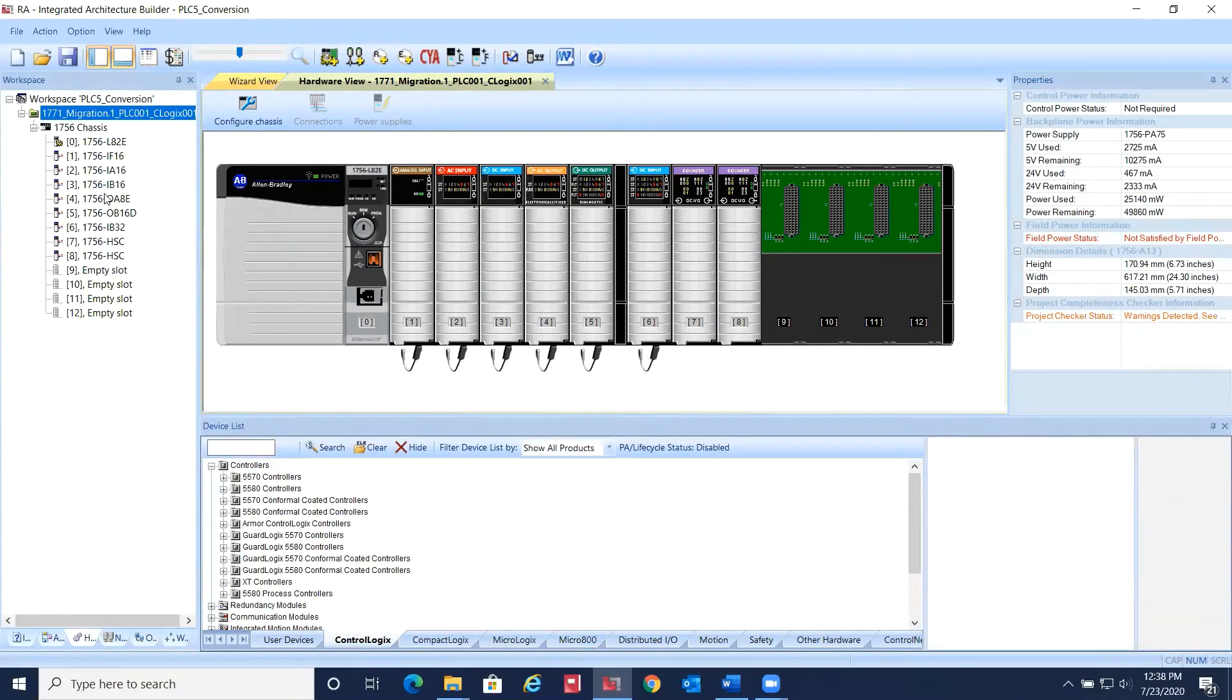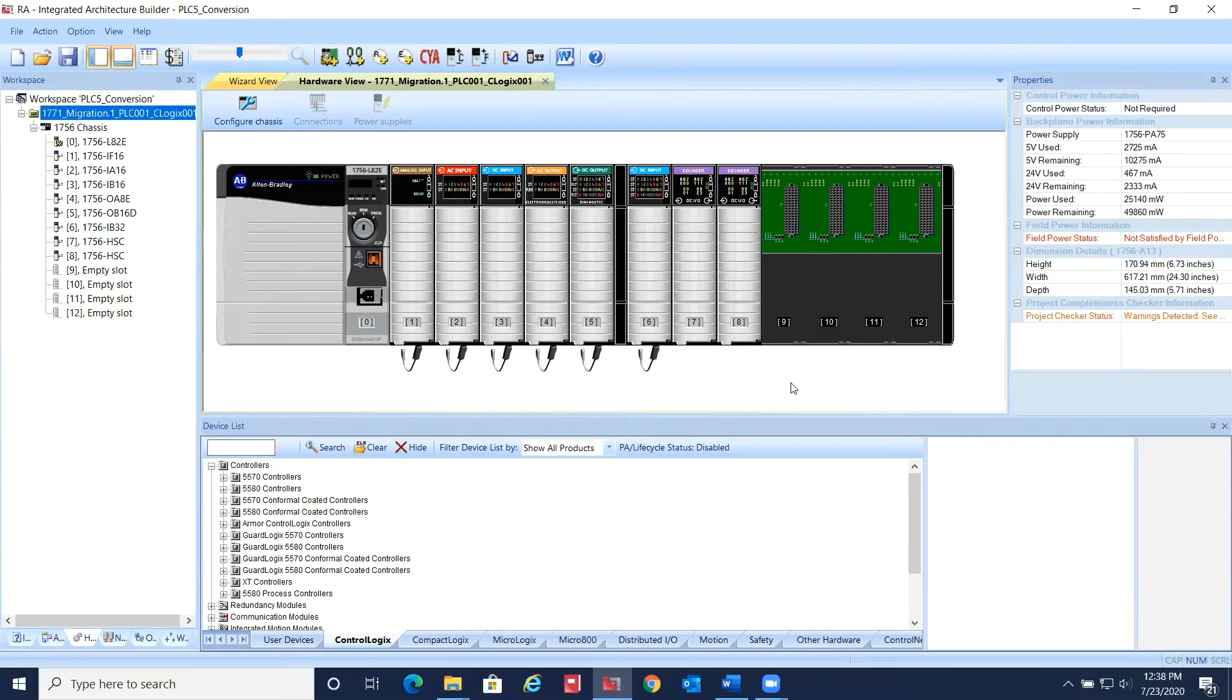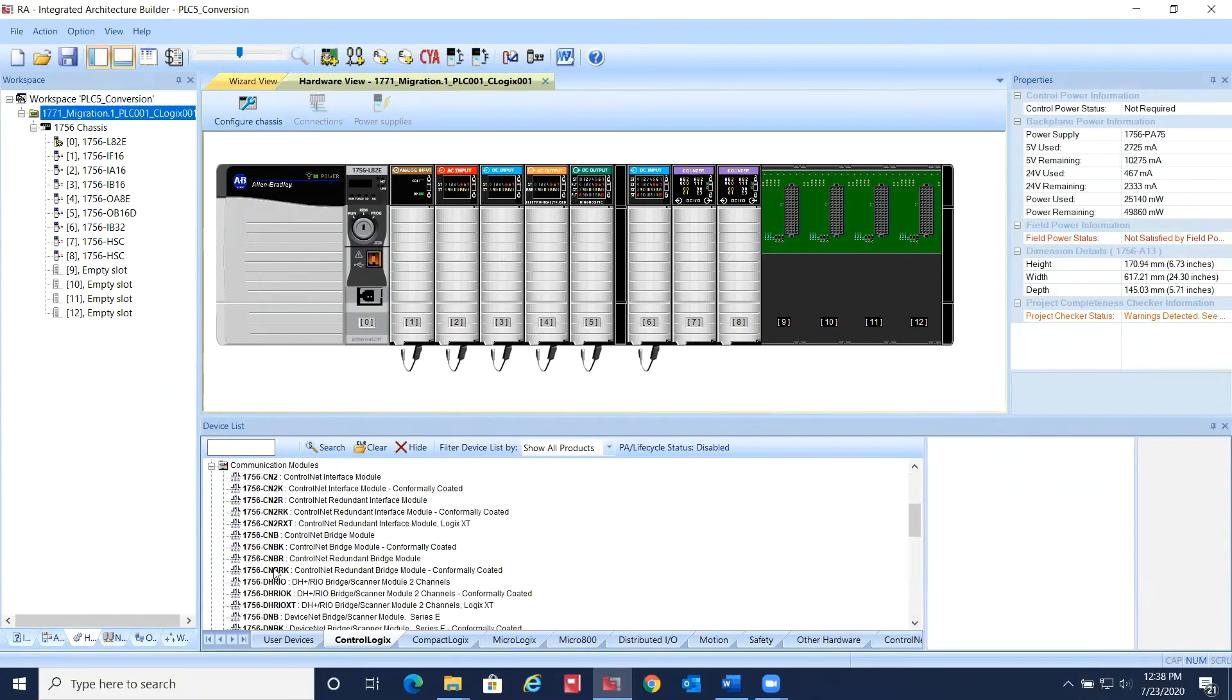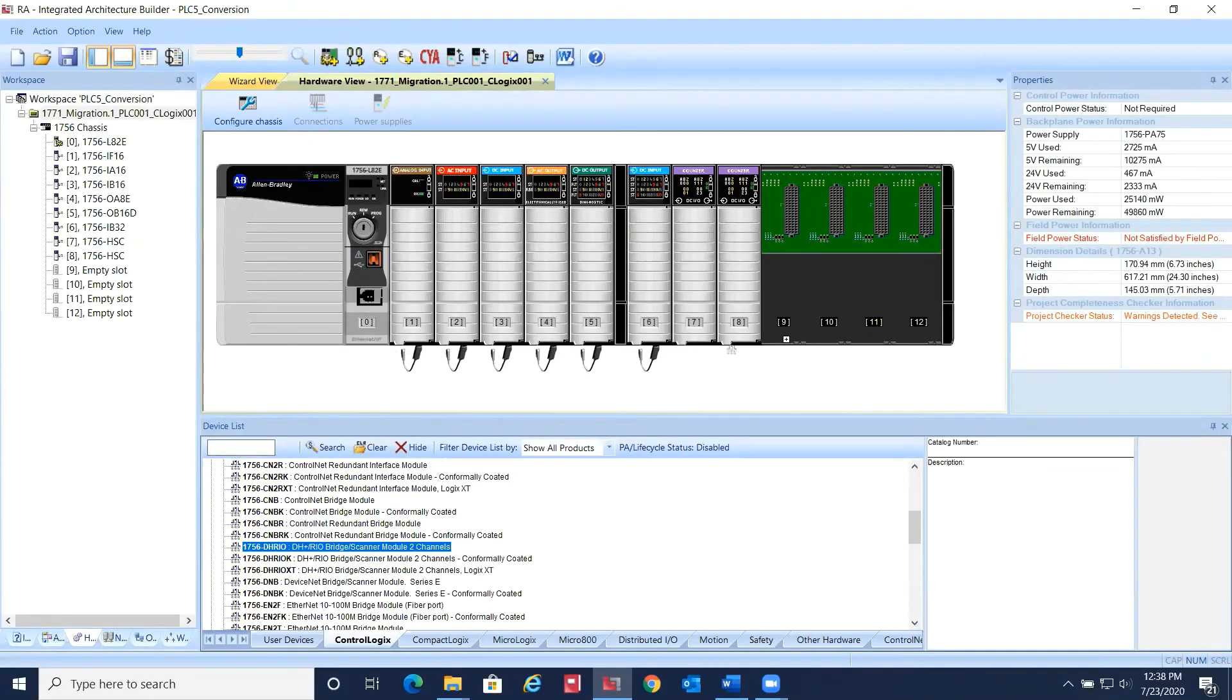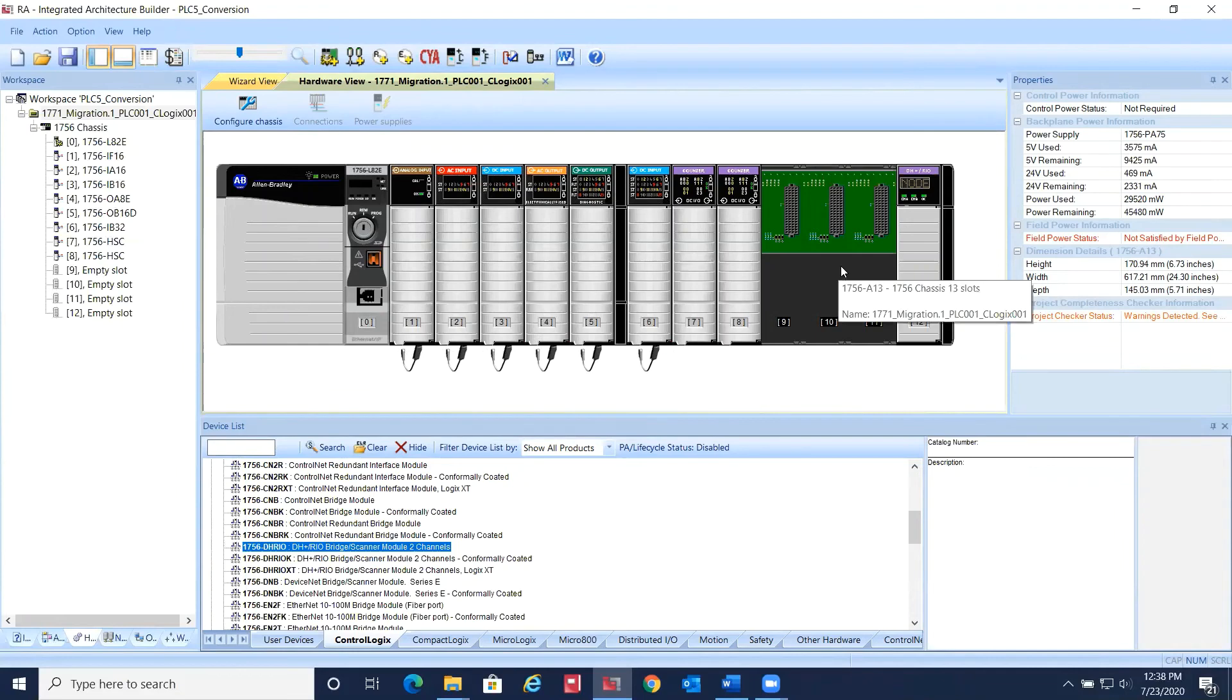Now let's add a couple more modules. If you have existing Remote I/O, you can add a 1756-DHRIO card to your ControlLogix chassis and use the existing Remote I/O hardware in conjunction with your ControlLogix chassis.